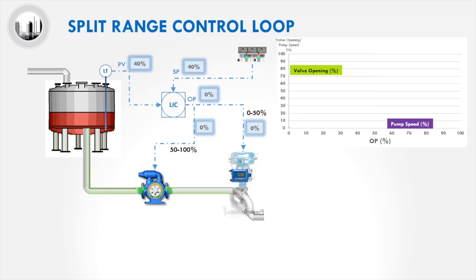This diagram shows a setup with split range control. The difference here is that the output of the controller now sends different signals to the control valve and the pump. The control valve will receive a 0 to 50% signal range, while the pump will receive a 50 to 100% signal range.